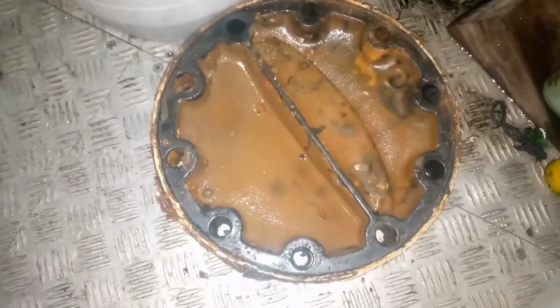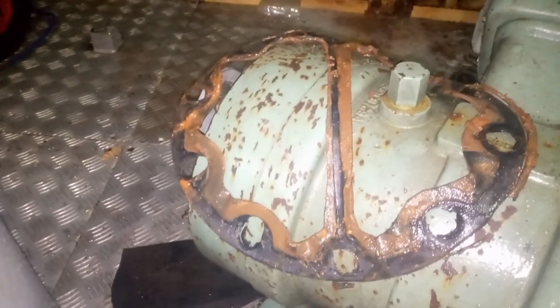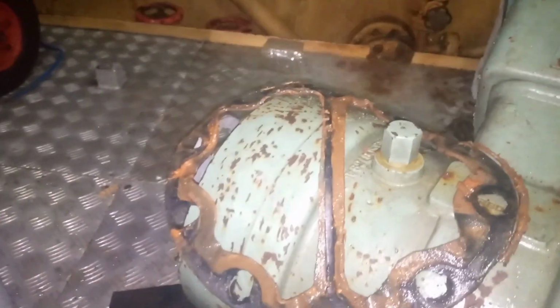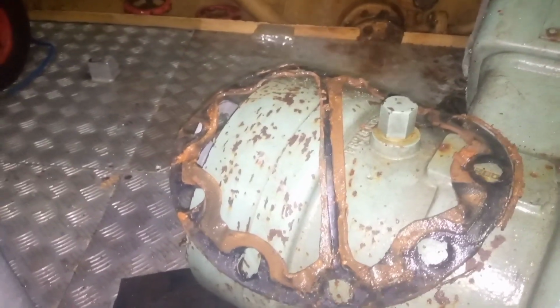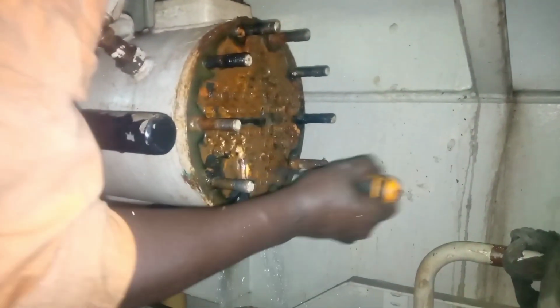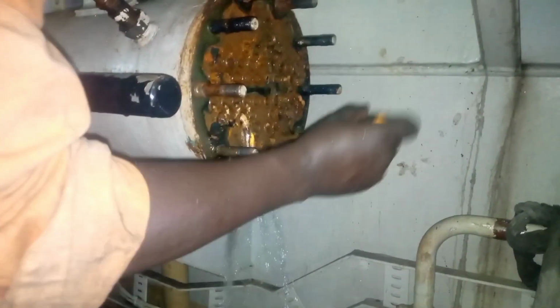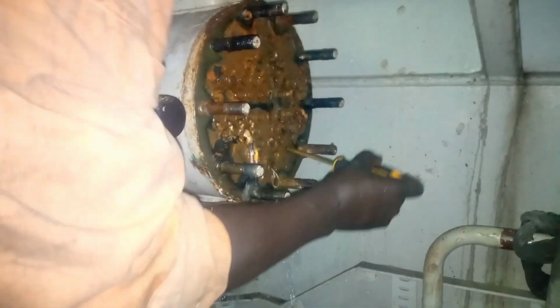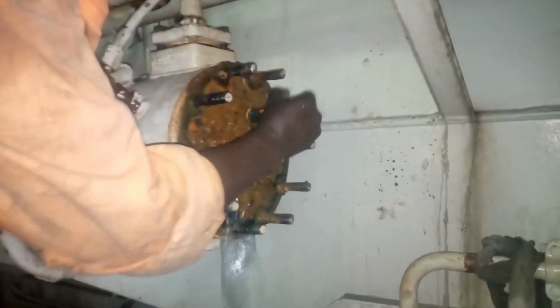Seawater causes corrosion within a very short period of time, and therefore it's very important to do this servicing frequently to these machines so as to ensure that they are not eroded and thus reduce their performance. You can use a screwdriver or a wire just to make sure that the ends of the heat exchanger tubes are not blocked with any foreign materials.